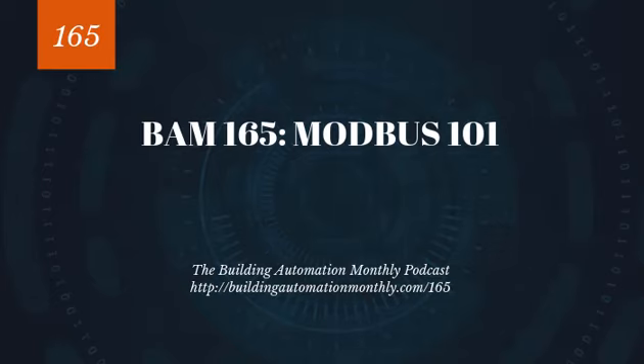It's crazy. So as I was saying, the Modbus ADU, and here's what I want you to picture here, has a field for additional addresses. If you've ever seen network packets and you've seen the different fields, time to live, source and destination MAC, etc., then you'll know what I mean by fields. So it's actually a field inside a message. And the ADU contains 4 fields: the additional addresses, as I mentioned, the function codes, the data, and then error checking.